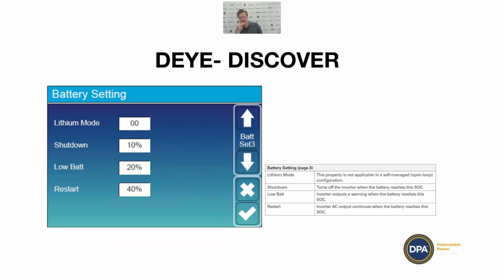I would recommend that you set these quite conservatively. I know that battery manufacturers advertise 100% depth of discharge for their batteries. And there can be a bit of confusion about that because some manufacturers might have a battery which is 5 kilowatt hours, but they advertise it as 4.5 or something like that. And so then you can use 100% of it. I don't think there's many of them doing that anymore.